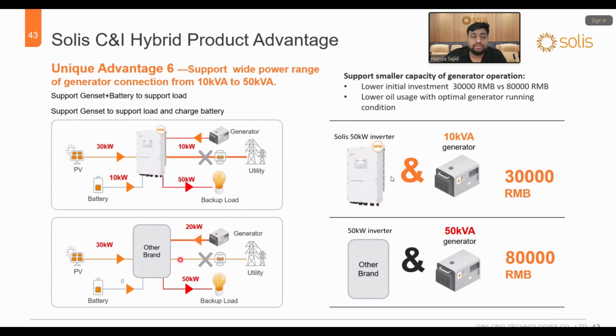But with other brands, you should connect at least a 20 kilowatt or 50 kVA generator, so it can take 20 from the generator and the rest of the power, 30 kilowatt, from the PV to support the load of 50 kilowatt. And this is the reference cost difference if you use Solis with a 10 kVA generator or another brand with a 50 kVA generator. Okay, so lower initial investment, 30,000 RMB versus 80,000 RMB, and low oil usage with optimal generator running condition.